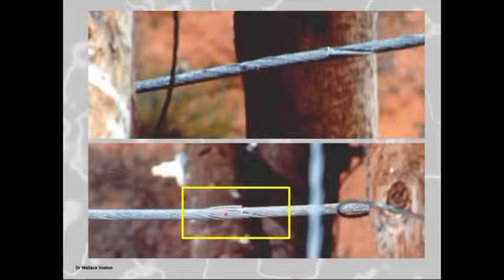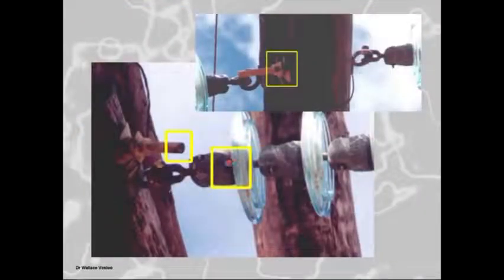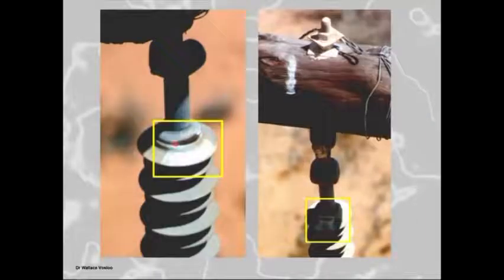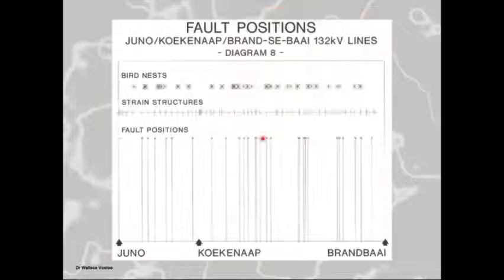We found the signs where it terminated. We could see broken strands where it terminated on the conductor. And we could also see on the insulators and the hardware where the actual arc terminated with a flashover. We could see it on the insulator. This here is a classical power arc termination with a power arc flashover, but you could see here with the bird excretion present, so this was the classical signs of bird excretion flashover on the composites.